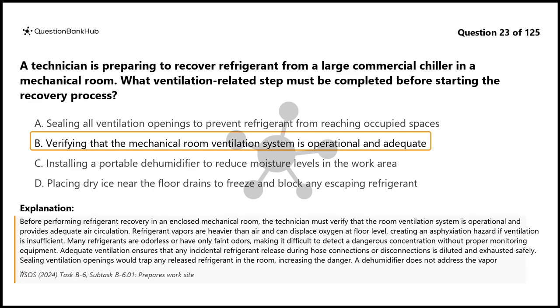Sealing ventilation openings would trap any released refrigerant in the room, increasing the danger. A dehumidifier does not address the vapor displacement hazard. Dry ice placed near drains is not a recognized safety procedure and would add carbon dioxide to the confined space, worsening the oxygen displacement risk.